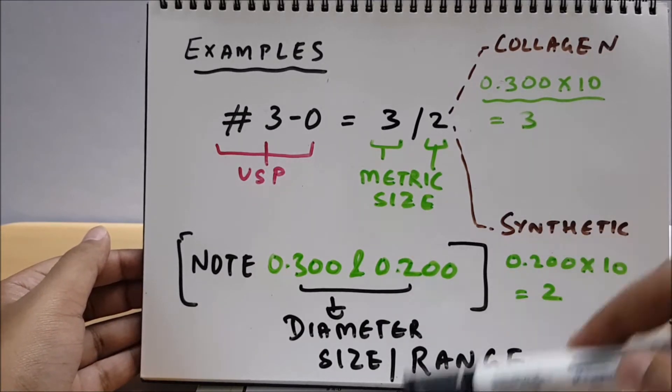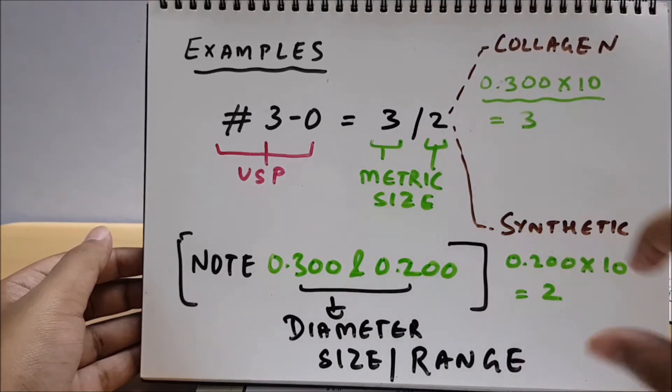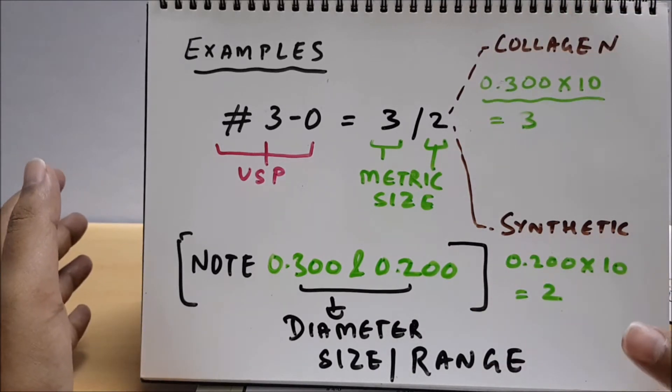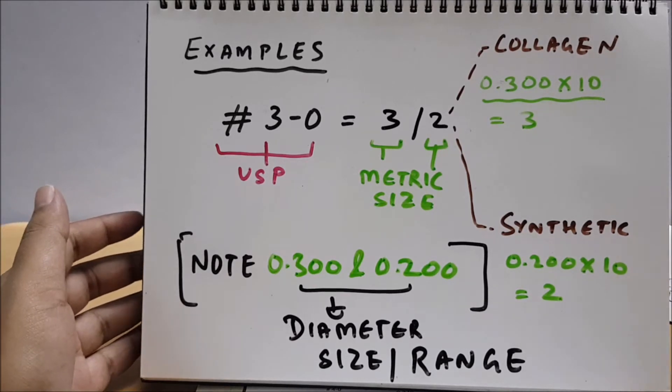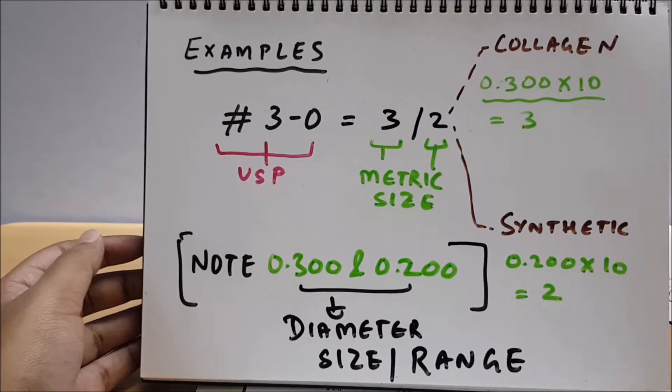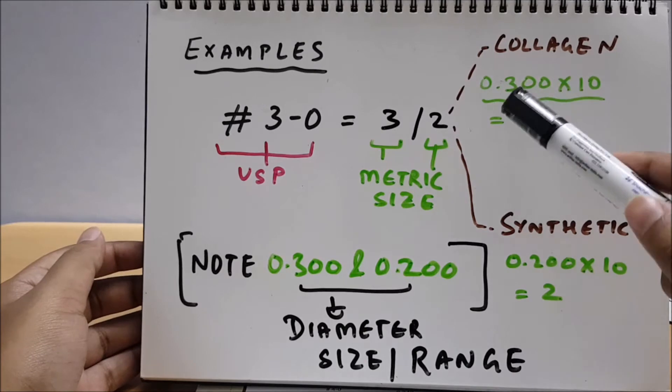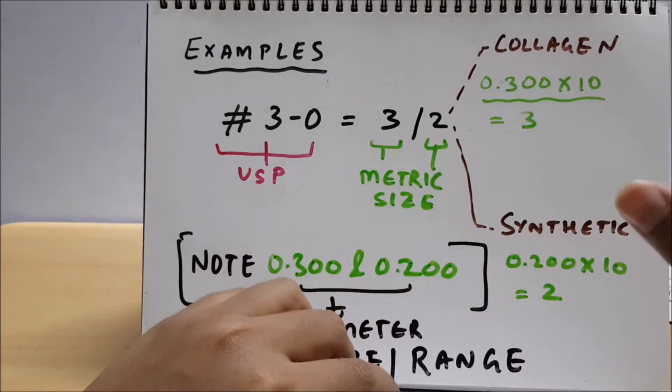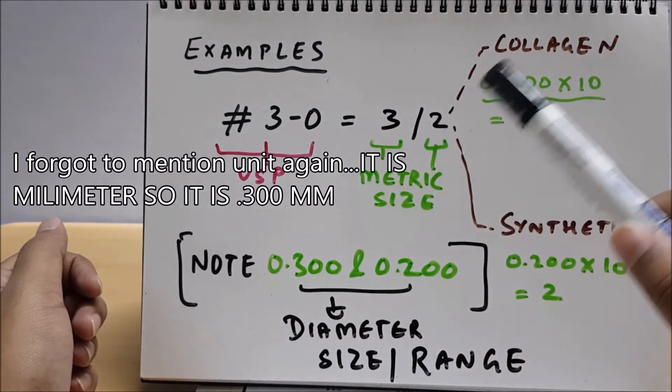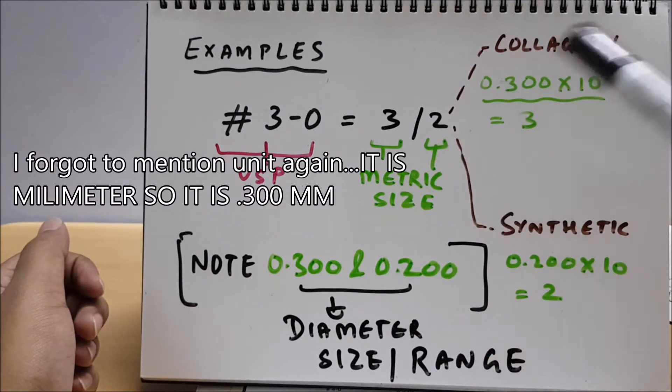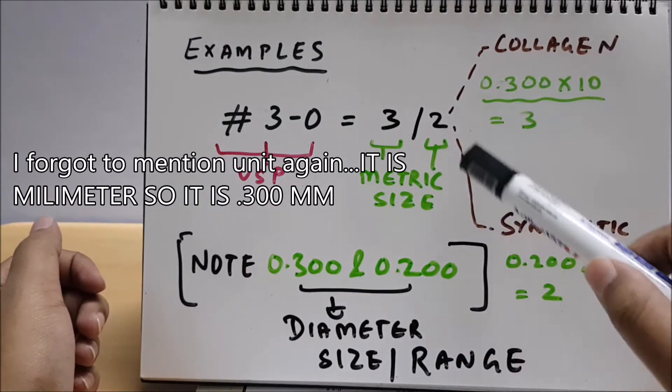See friends, all these things are completely defined by the company manufacturing them. We'll see the chart also that will really clear your confusing part of this. Let us see collagen: the diameter of that collagen suture is 0.300. So we'll multiply by 10 - it will come 3. That's why the metric size of collagen suture is 3, which is 3-0 in USP nomenclature.